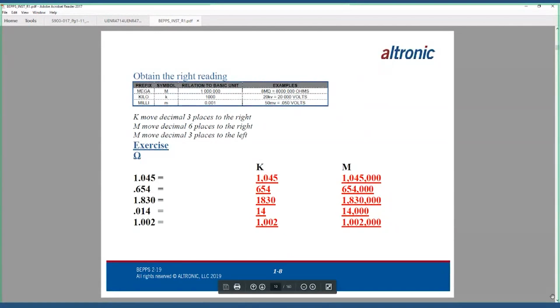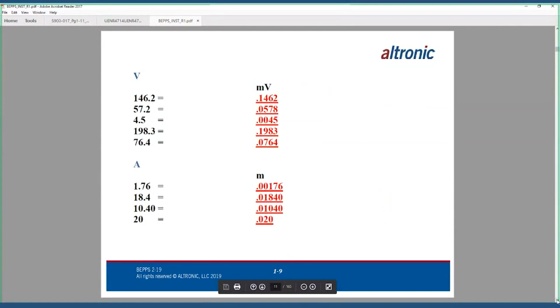Now, I think I got a good example of milliohms on the next page. Well, millivolts, same thing. Now, here's milliamps right down here at the bottom. So 1.76 milliamp, we would move the decimal place the opposite direction, so it becomes 0.00176 amps is how we would call that out. So a good example is, more than likely, anybody on this call has heard of the term 4 to 20 milliamps.